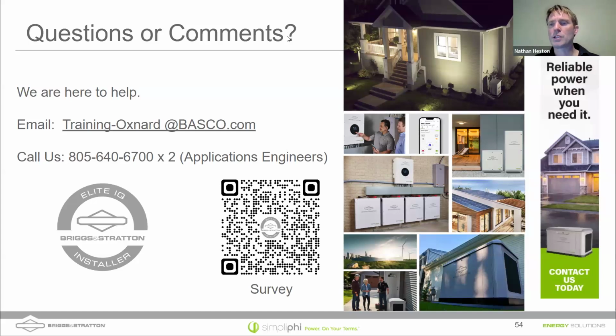Russ says, normally our transfer switch has a safety to keep electrical current from backfeeding to the grid. What safeties do we have for a battery being charged and a power outage occurs? How does the system know what is happening and to understand the difference? So any 1741 or 1741 SA or 1741 SB certified inverter is required to not island, right? To prevent islanding, and that means preventing that Sol-Ark from being connected to the grid, preventing that inverter from feeding power back onto a grid in a down situation. So how it knows what is happening, it's continuously monitoring the L1 and the L2 of the utility port, and it anti-islands in a grid down situation. I'm not sure I can give much more information, so feel free to clarify if I didn't answer that very well.